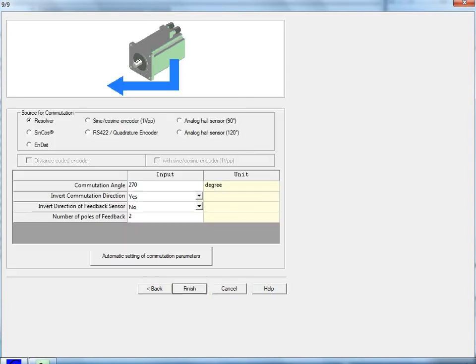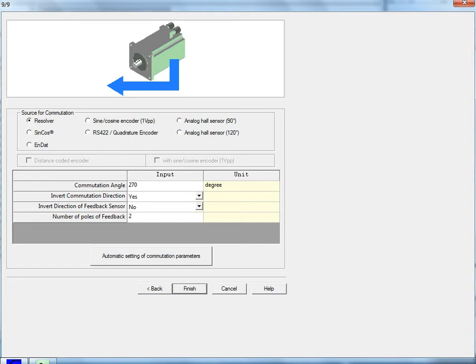Step 9 sets the motor feedback. The radio button at the top selects the feedback type. These are straightforward except for the SinCos®. That's a trademark name for Stegmann's Hyperface Absolute Encoders. This shouldn't be confused with the Heidenhain EnDat, which is also a sine-cosine type feedback signal, or a 1-volt peak-to-peak sine-cosine encoder.